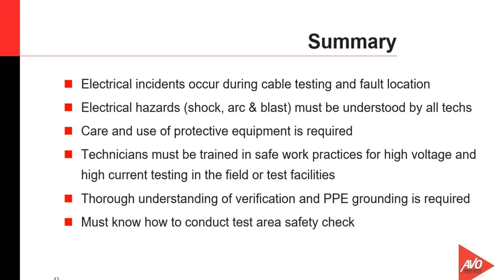A thorough understanding of verification and grounding is required, and we still have a lot of incidents involving the lack of proper verification of the system itself. Remember, you have to check all 3 phases. The meter has to work, so that's the other issue with it. And PPE grounds have to be engineered. They have to be designed based on the short circuit and coordination studies, so they have to be rated for the short circuit and the duty that they're actually going to be expected to have.